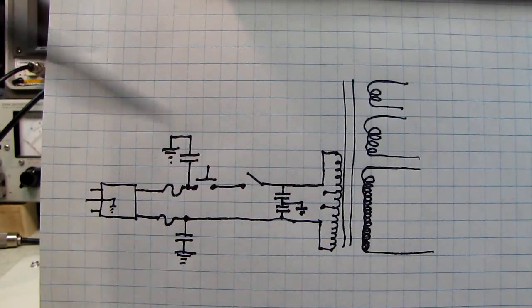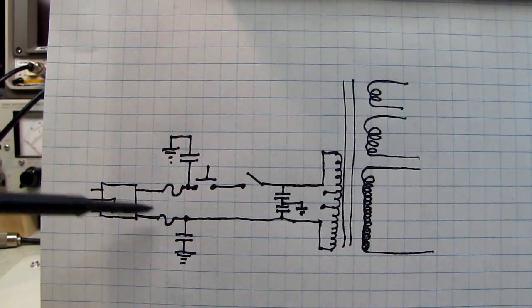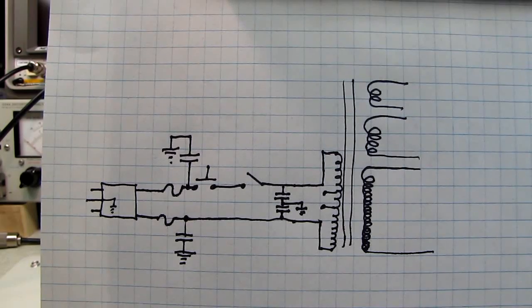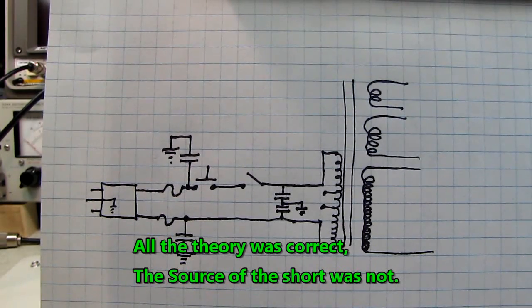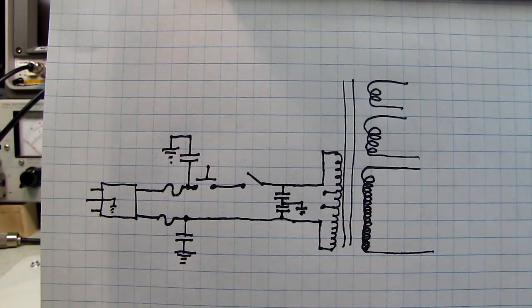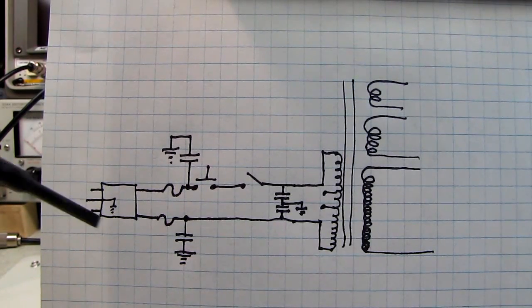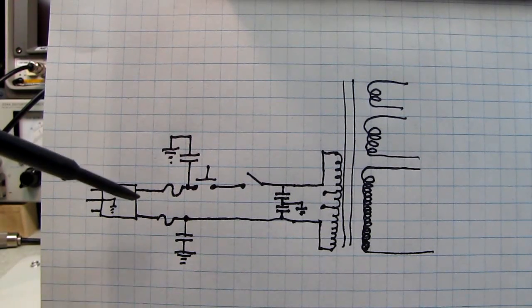When you close the main power switch, it doesn't blow either fuse. So the leak has got to be bad enough to pull enough current to light the lamps up and slowly run the fan, but evidently isn't quite bad enough yet to blow the fuses, or a fuse. It's fused on both legs. These are 12 amp fuses at 220 volts. They'd be 20 amp fuses roughly at 115.